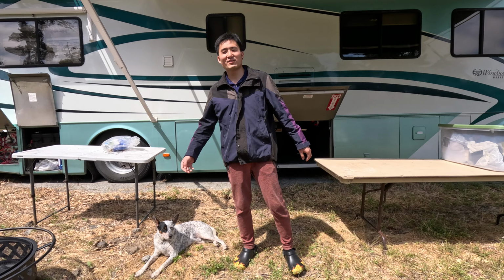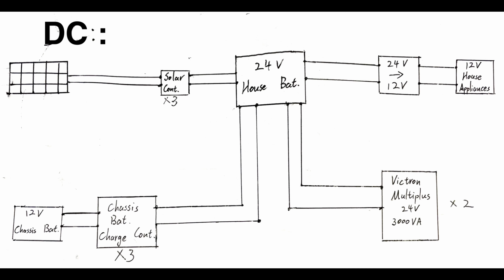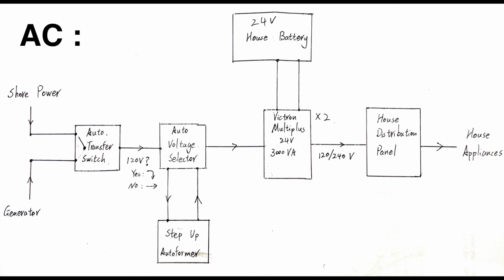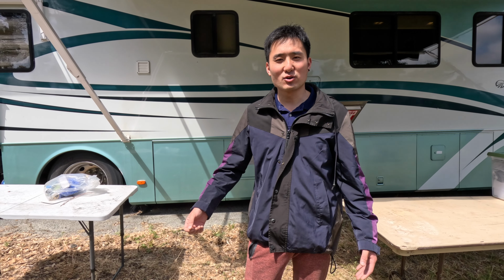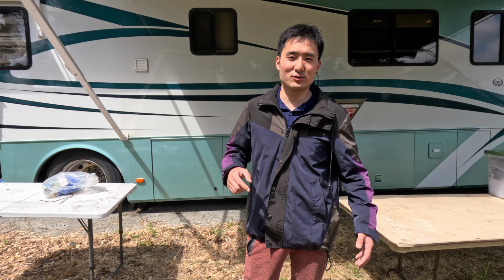To give an overview, we have 3,800 watts of solar panels on the roof with a slider system. The battery, we've got 620 amp hour at 24 volt, that's our house battery. The inverter system, we've got two of the Multiplus 3,000 volt amps, consisting of 6,000 volt amps at 120 and 240, the US house voltage. Also we've got more than 200 amps of 24 to 12 volt voltage converter to feed the house side of the electronics.